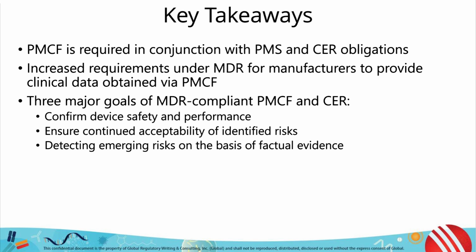Ultimately, PMCF must be addressed under the MDR, and the requirements for PMCF are much stricter than under MDD. The main goals of PMCF are to confirm device safety and performance, ensure continued acceptability of identified risks, and detect emerging risks on the basis of factual evidence.